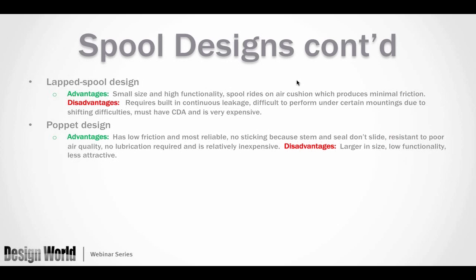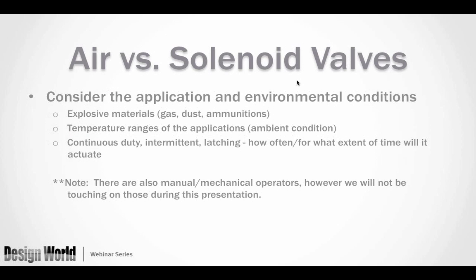Advantages of the poppet design include low friction, reliability, and no sticking since the stem and seal don't slide. When considering air versus solenoid valve actuation, air is intrinsically safe — so if you have an explosive atmosphere, whether from gas, dust, or other hazards, an air-piloted signal may be the best choice because a solenoid-controlled valve has electricity and the potential for sparking.